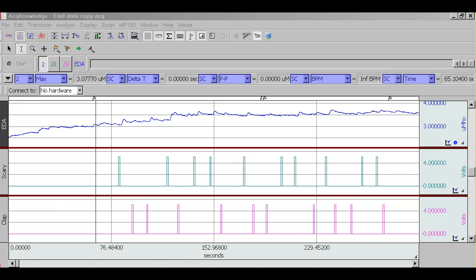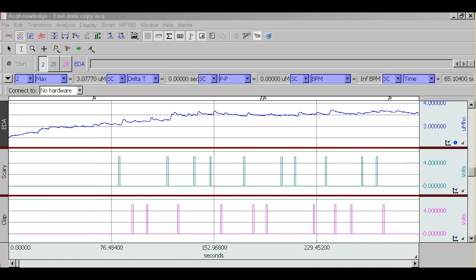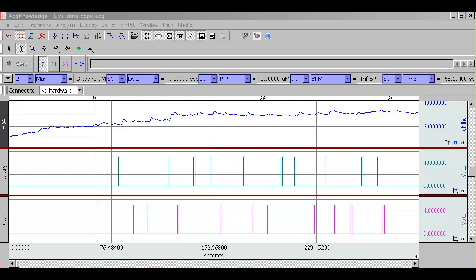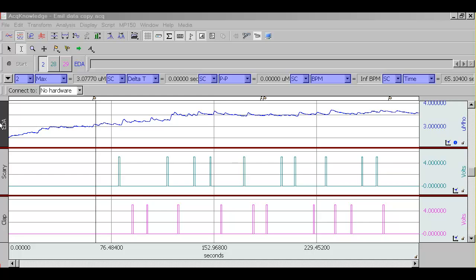You need a recording where we have both the skin conductance data and markers that correspond to the stimulation events. You can send digital markers over the parallel port using a program such as E-Prime, DirectRT, or SuperLab. What you get is these new channels, as you can see below here, underneath the skin conductance data.